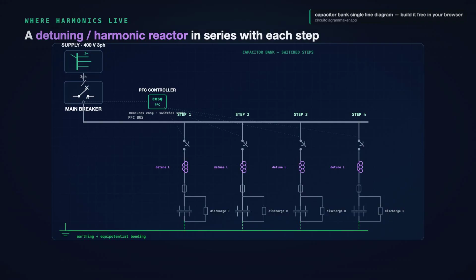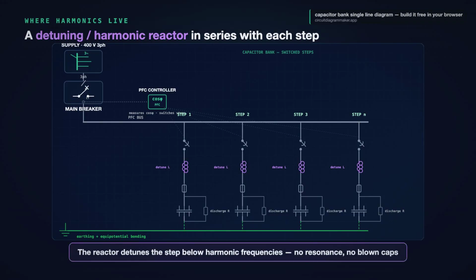Now, one more device the one line has to tell you about, where harmonics live, the detuning or harmonic reactor. In a plant full of variable speed drives and rectifiers, the supply is full of harmonic currents. And a bare capacitor bank is dangerous around harmonics. It can resonate with the system, amplify those currents, and blow the caps. The fix is a reactor in series with each step. The same inductor position we use for inrush, but now sized deliberately to detune the step.